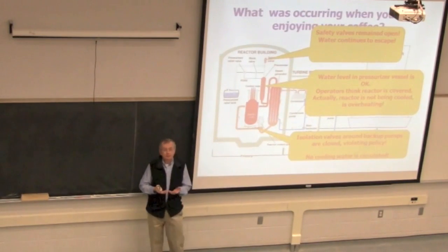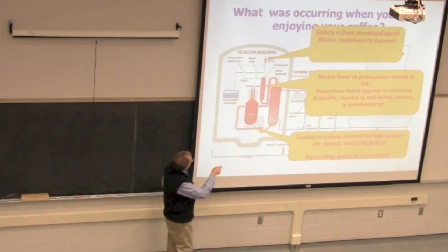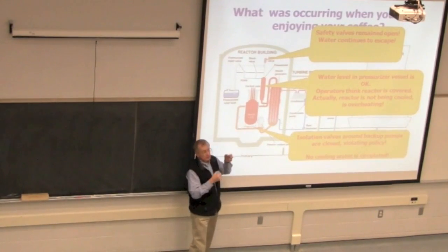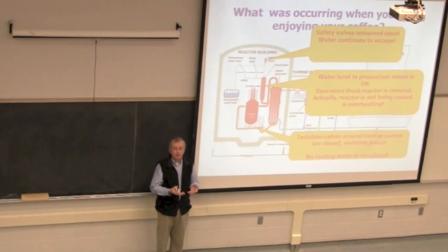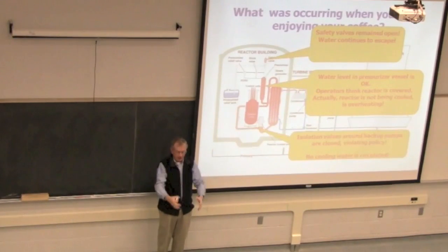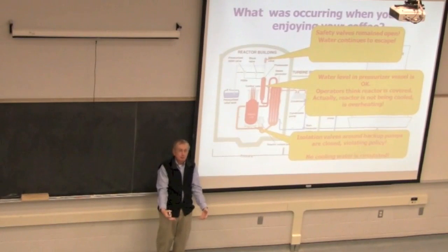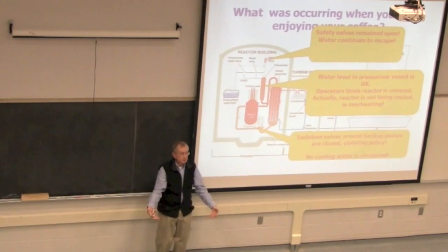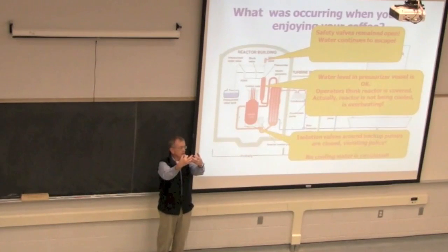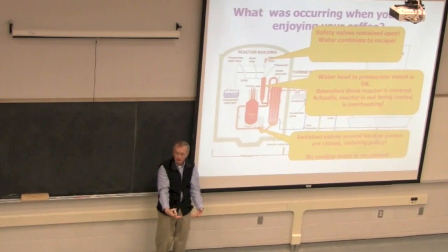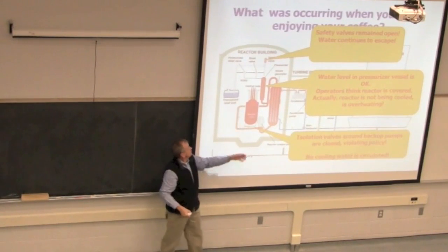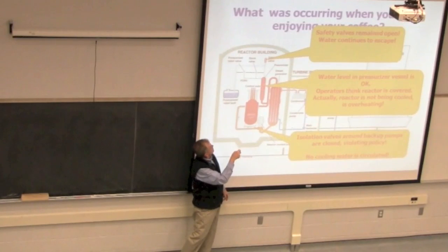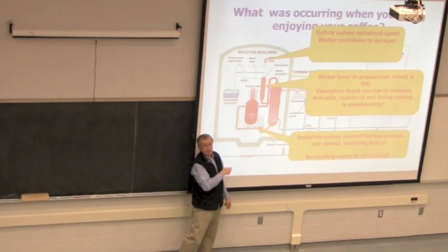We're boiling the water. Okay, so in this whole system, this pressurized water system, the reactor's gotten so hot that we're boiling the water. So if we think of a big column of water, if I put heat down in the bottom and started to boil the water, what would happen to all of the liquid? It would kind of get pushed up. This vapor would be rising and pushing the water up. So even though it's boiling and there's no water down at the bottom or not enough water down at the bottom, it's pushing the water up so that there isn't water interface here, but there's no water down here, not sufficient to keep the reactor cool.